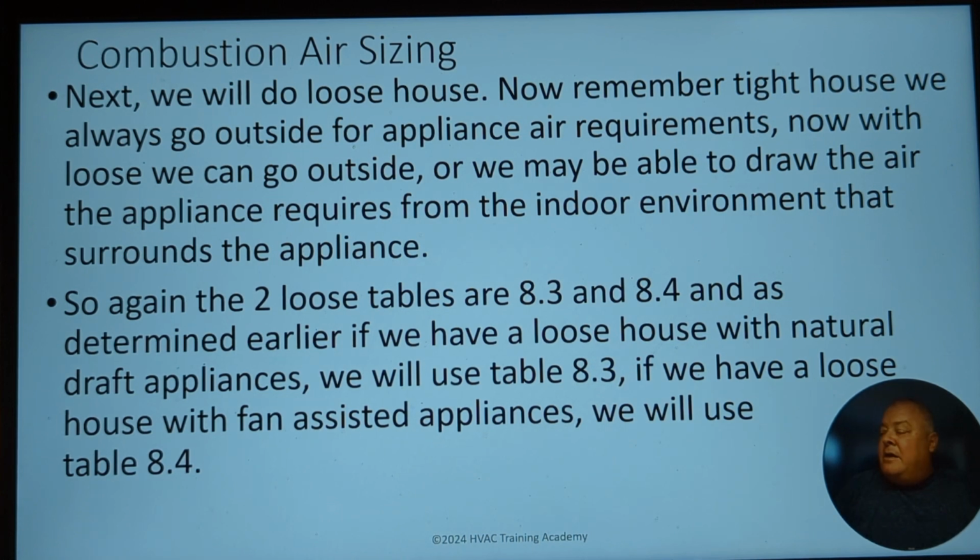So it was pretty easy when it came to combustion air sizing on a tight house. Because you knew you were going outside, it was just a matter of calculating how many BTUs we had in that space, and then looking it up on our table to determine how big our duct has to be between the outdoors and the room that the appliances are installed in. Now with the loose house, it's going to be a little more complicated.